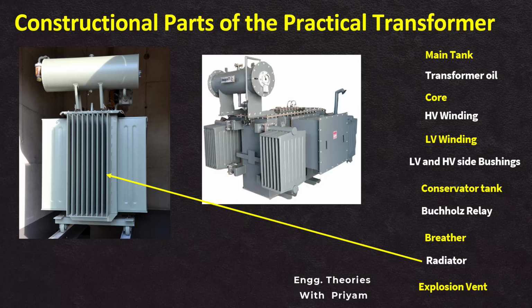The next component we want to talk about is the explosion vent. An explosion vent in a transformer is placed to enhance safety in the event of a fault leading to a sudden increase in pressure. Typically located on the transformer tank, the explosion vent is designed to release excessive pressure caused by an internal fault, preventing catastrophic failure. In operation, if the pressure within the transformer rises to a critical level due to factors such as a short circuit or an electrical fault, the explosion vent opens, allowing the release of gases and pressure.